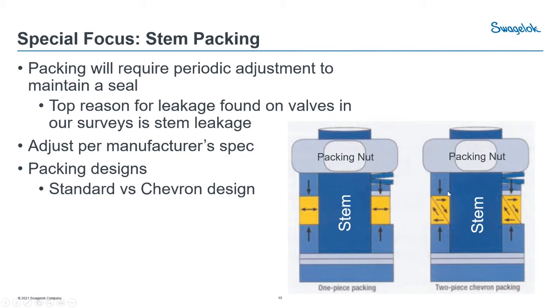One more note: if we over-tighten packing. We want to tighten to spec — why use a torque wrench rather than just going as tight as possible? Because over-tightening squeezes more on the stem, creating more friction and drag, potentially making the valve hard to open. Furthermore, if you ever need to change out the packing or rebuild the valve, never loosen a packing nut when the valve is under pressure. Doing so will unload the valve and you can have a material leak immediately. Never reduce tension on the packing nut unless the valve is fully isolated and depressurized — it can be a very dangerous situation.